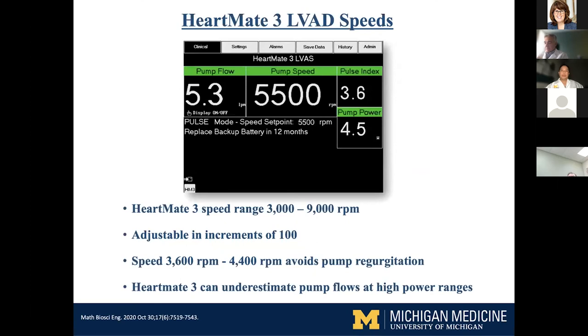The HeartMate 3 can range in speed from 3,000 to 9,000 RPM, although I've never seen anyone use 7,000, 8,000, or 9,000 because the pump is really over-engineered for providing flow for human physiology — which is good. It's adjustable in increments of 100 RPM, and at speeds of around 4,000 RPM, you're essentially treading water and just avoiding pump regurgitation.